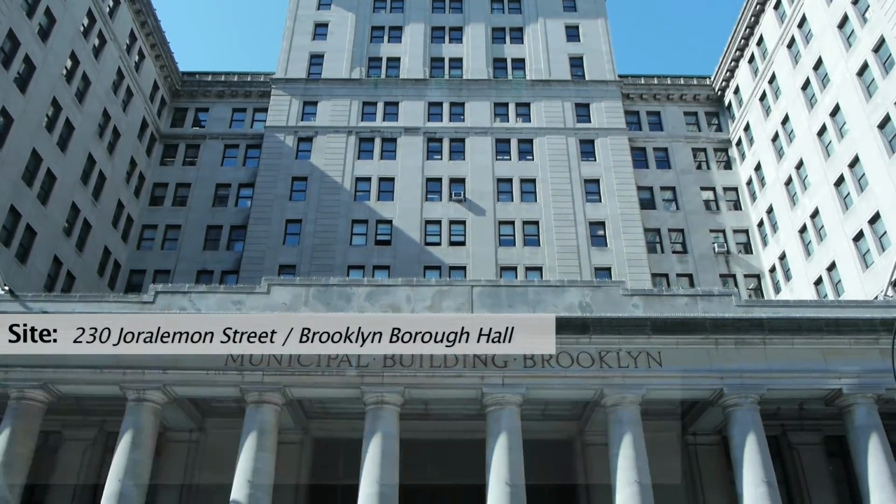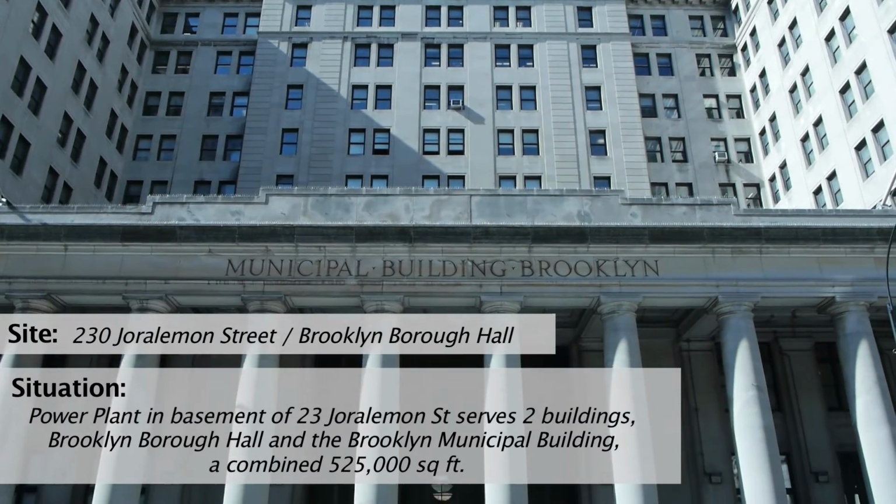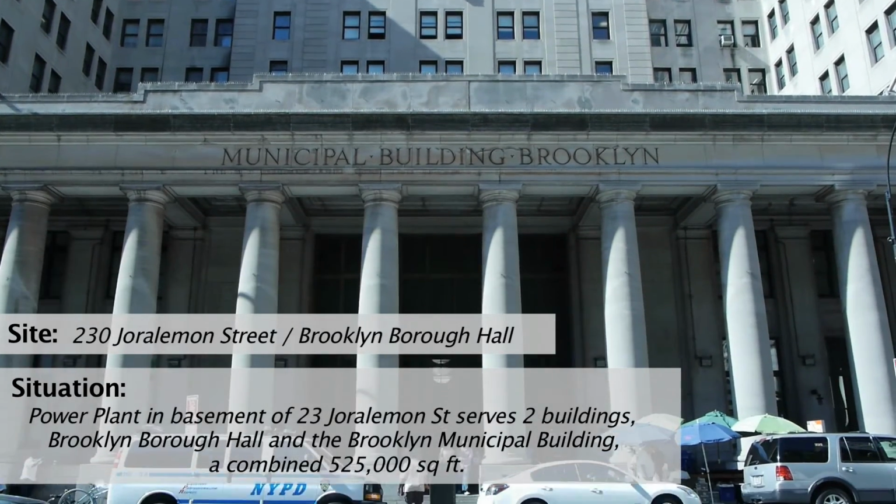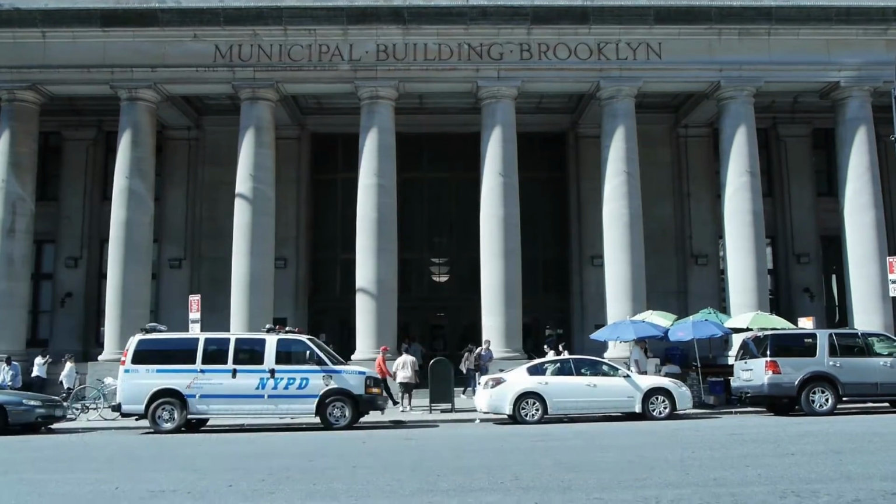It was the summer of 2010, my first summer here. We started up the chiller plant and the chillers were running unloaded. We had a delta T of approximately 4 degrees. So we were putting out 45 degrees. We were returning on the primary loop about 49, and yet we were supplying 52, 53 degree chilled water to the two secondary loops and the tertiary loop to Borough Hall.